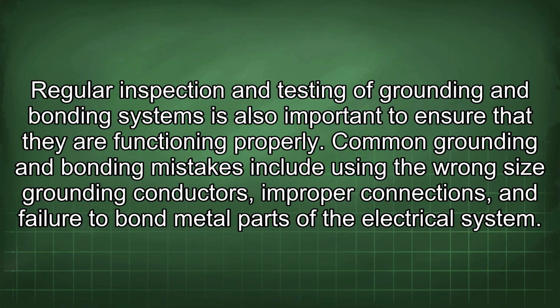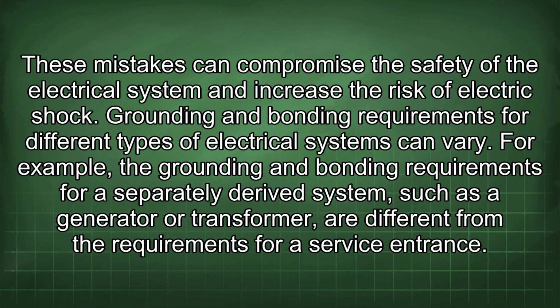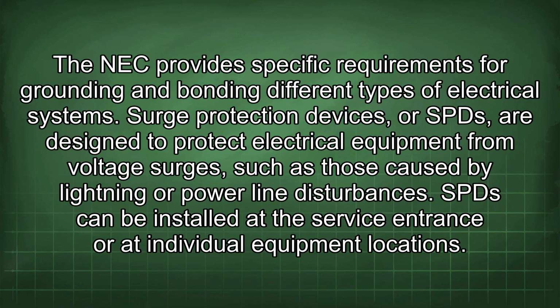Common grounding and bonding mistakes include using the wrong size grounding conductors, improper connections, and failure to bond metal parts of the electrical system. These mistakes can compromise the safety of the electrical system and increase the risk of electric shock. Grounding and bonding requirements for different types of electrical systems can vary. For example, the grounding and bonding requirements for a separately derived system such as a generator or transformer are different from the requirements for a service entrance. The NEC provides specific requirements for grounding and bonding different types of electrical systems.